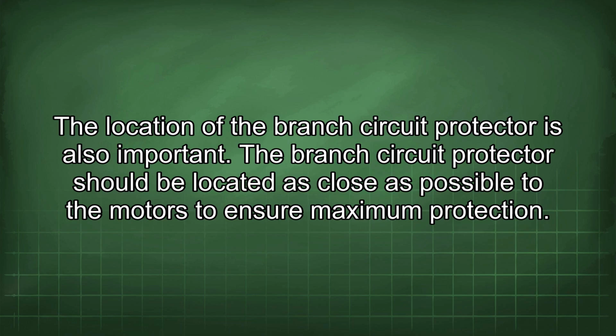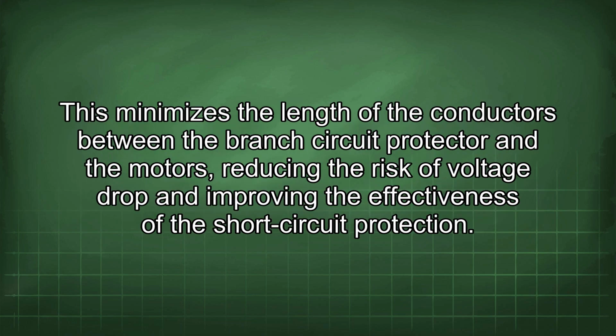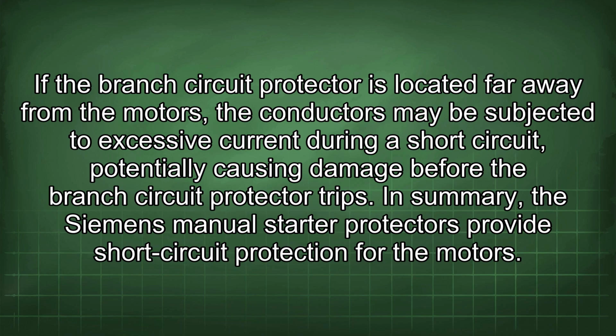The branch circuit protector should be located as close as possible to the motors to ensure maximum protection. This minimizes the length of the conductors between the branch circuit protector and the motors, reducing the risk of voltage drop and improving the effectiveness of the short circuit protection. If the branch circuit protector is located far away from the motors, the conductors may be subjected to excessive current during a short circuit, potentially causing damage before the branch circuit protector trips.